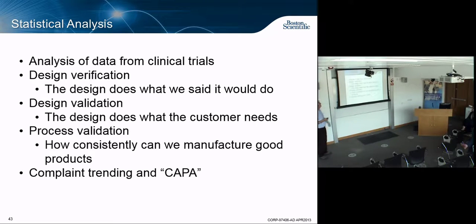Quickly on stats: we are a highly regulated industry, dealing with FDA, European regulatory agencies, and the Irish regulatory agencies. We do design verification — does the device do what you said it would? Design validation — does it do what the doctor and patient want it to do? Process validation — once I've designed it, can I actually build it reliably? And complaint trending with CAPA — corrective and preventive action — if we get a spike in complaints, we investigate the root cause and fix it.